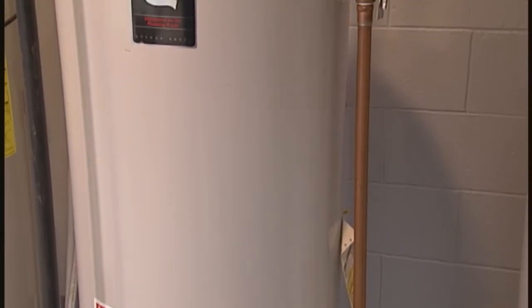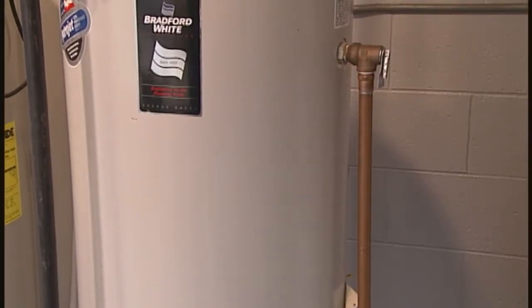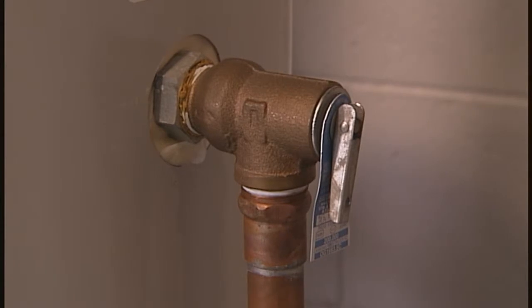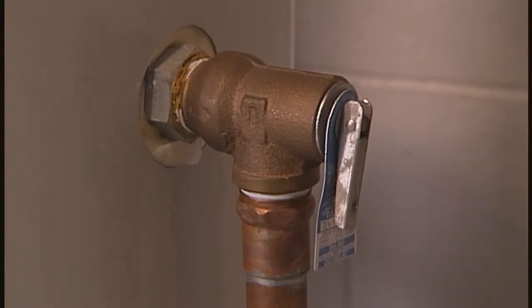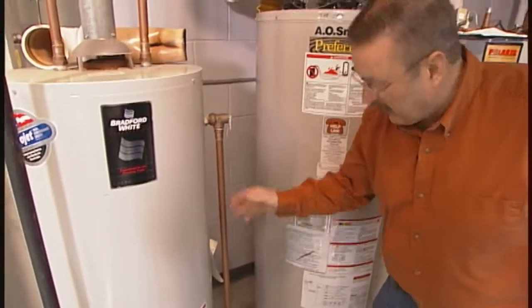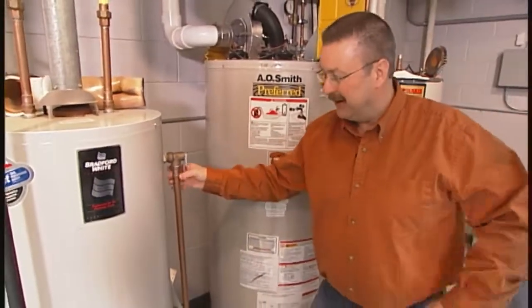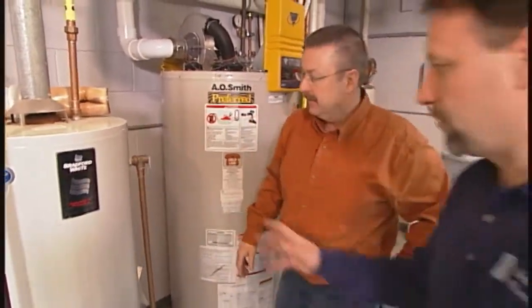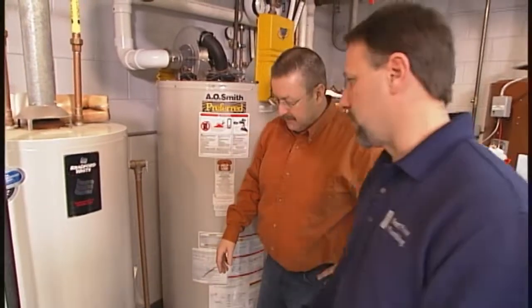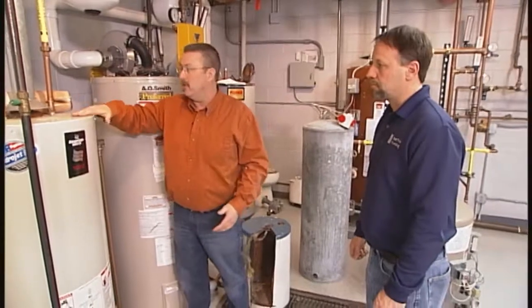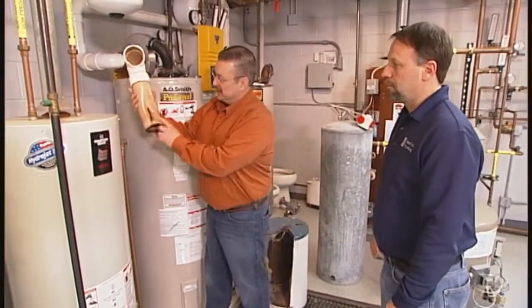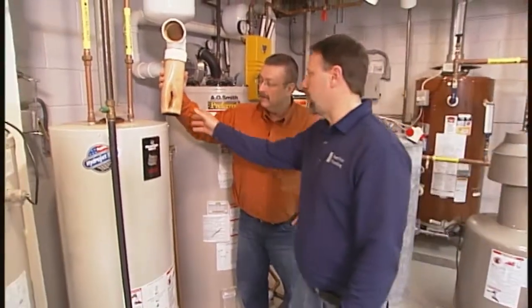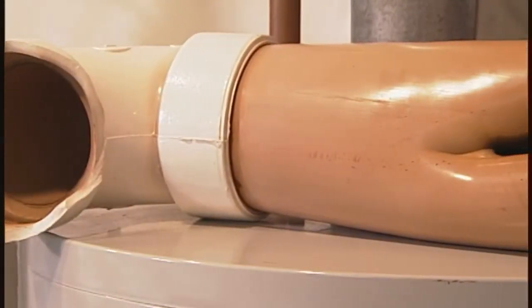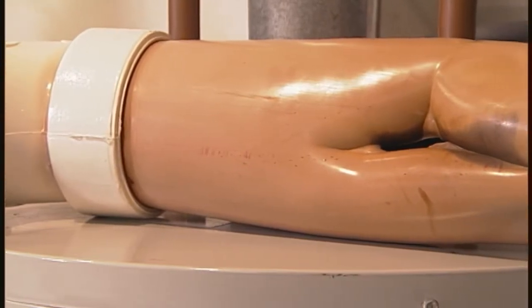A TP valve on the side, if it builds up too much pressure, is made so that it will blow off and go onto the floor. And I know a pressure relief valve, if you see any water leaking out of here, you should never under any circumstance cap it off, correct? That's correct, because if you do, you could have a small explosion in your house. Unfortunately, a lot of homeowners think they can just run down to the hardware store or the big box store, pick up a water heater, and install it themselves. But judging by this vent, this is what can happen if you do it incorrectly? That's correct. You'd never want to stick PVC pipe on a B-vent water heater; that's strictly made for a power vent water heater.